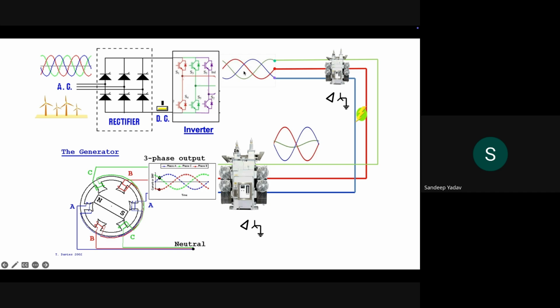So when you see the output of the voltage source converter, it is kind of decoupled from the input of the machine. So depending upon the control algorithm, depending upon the way we switch these inverters, that decides what kind of fault current it will feed, what kind of short circuit response it will have.